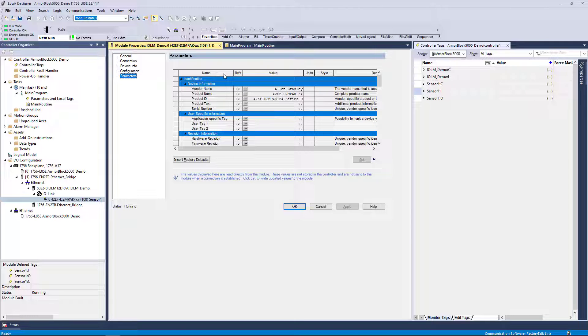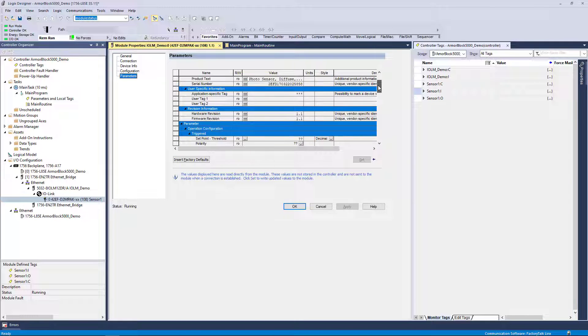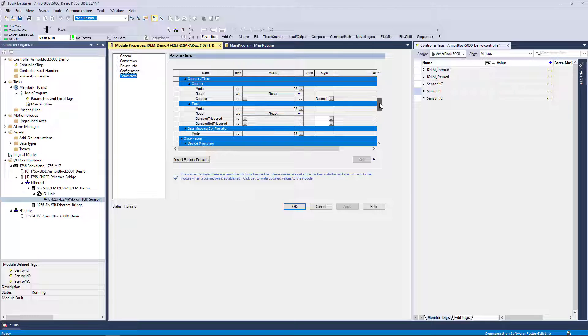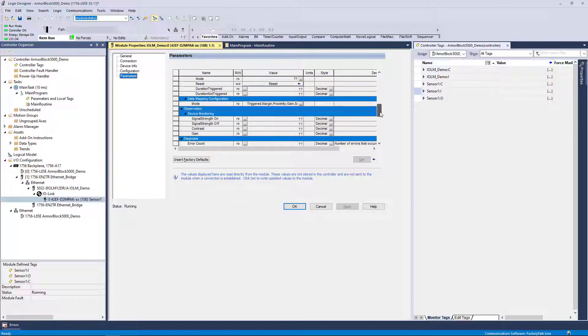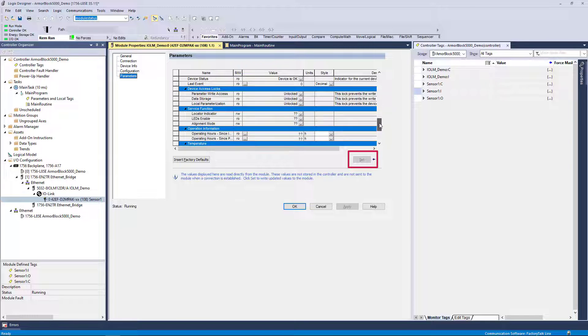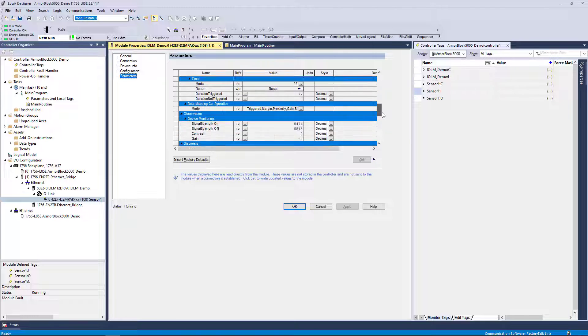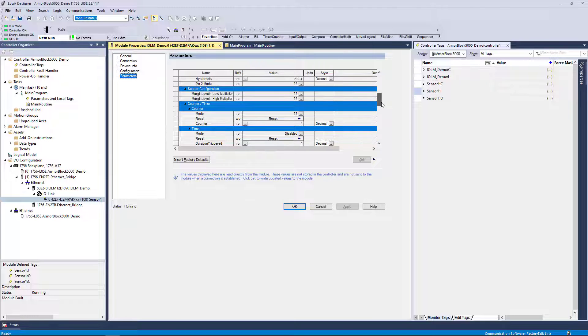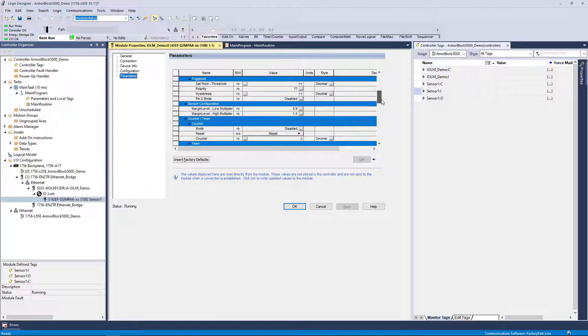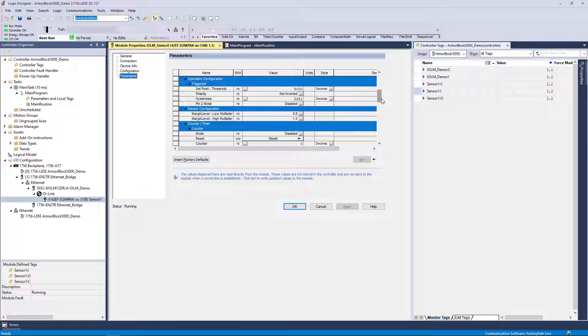The Parameters tab generally provides a read-only view of the running values and configuration within the IO-Link device. You can also set values for parameters that support write functionality. Let's focus on a specific value: the sensor set point threshold. This value represents the sensitivity of the photo eye within this project. We can see that the value within the device is at 9000 units. In the Parameters tab, we are not able to change this value.